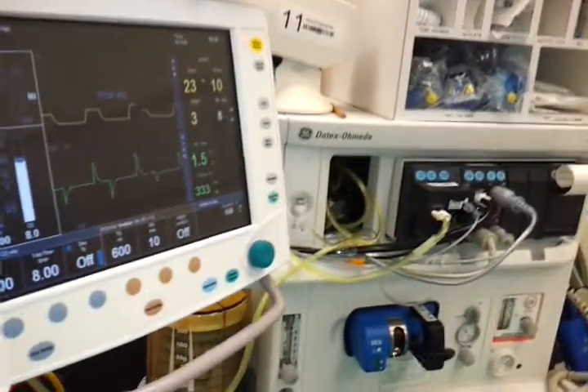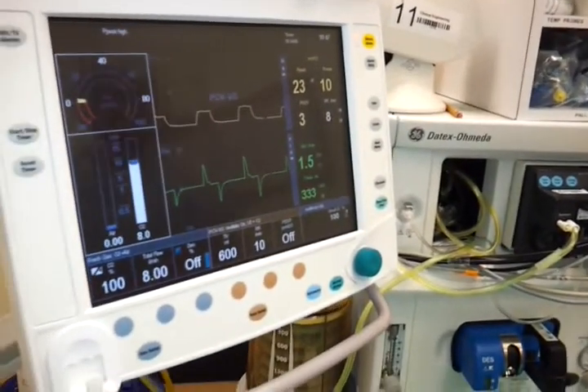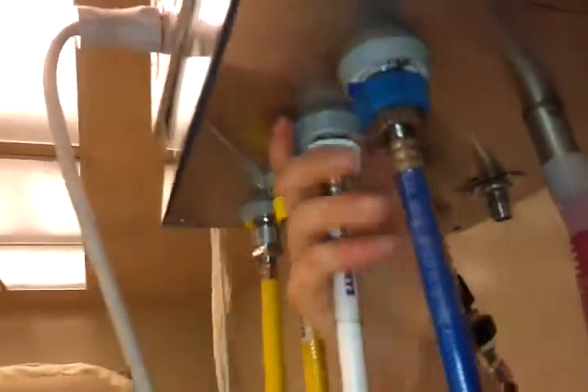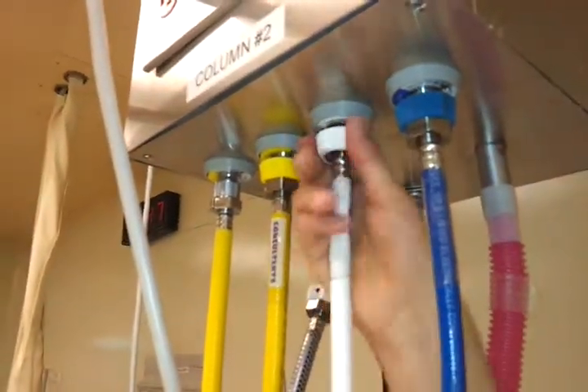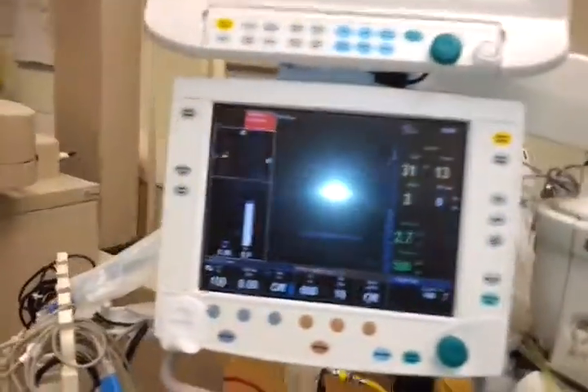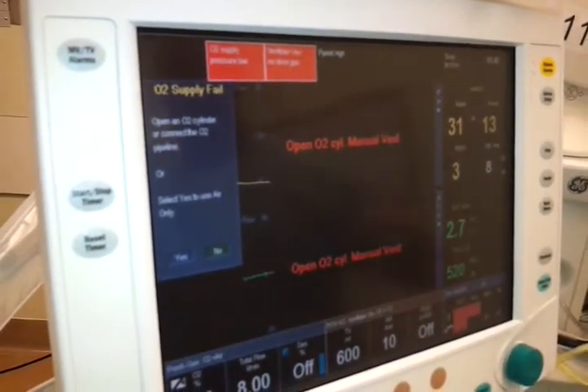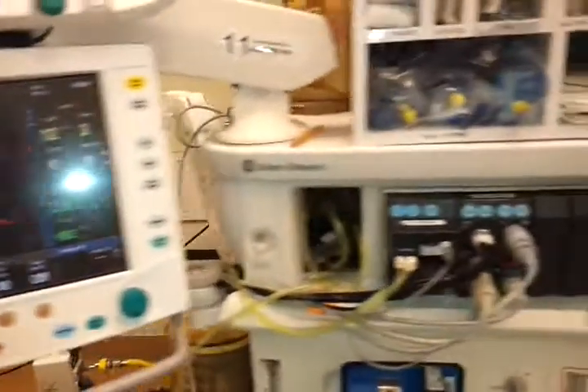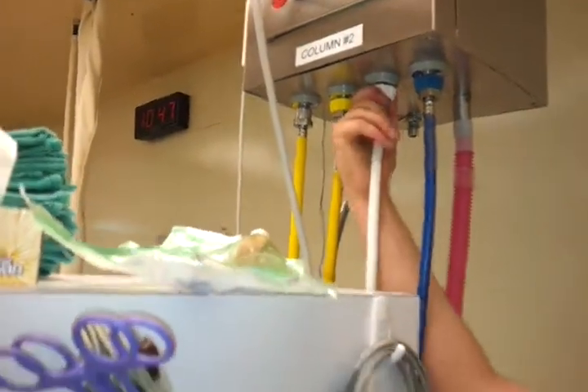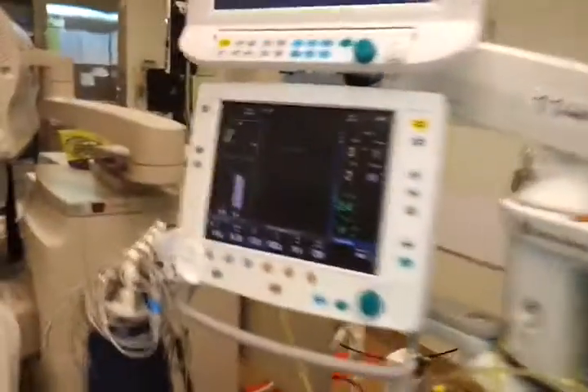So you have to test 4 alarms in the vent mode. The biggest one is in the back, the oxygen failure alarm, which is right up here. You have to disconnect that. Okay, so we're going to go around to the front. It's going to give you an audible and visual alarm. It won't let you do anything until you either hook up the cylinder or fix the problem. So I'm just going to hook it back up. Okay, so that should go away. So you always have to make sure that's working.